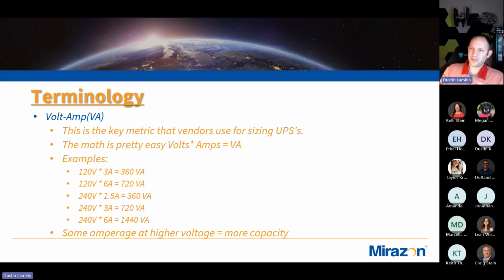But if you switch up to 240 volts, like we do in the data center, then that same 360 volt amps gets there by doing 1.5 amps. Generally in the data center, we're going to be pulling 240 volts; it's a lot more efficient, so that's why we like to use that higher voltage. So the same amperage at a higher voltage is more capacity.